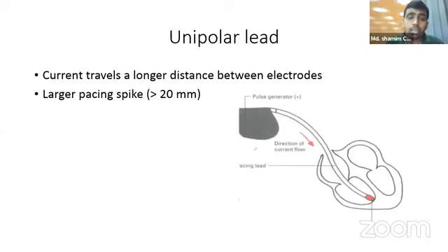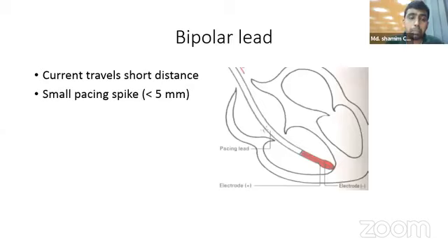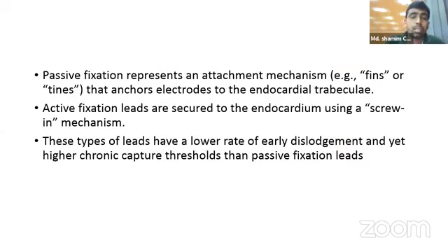This is a pictorial of the unipolar leads, which have larger pacing spike, more than 20 millimeter. And this is a bipolar lead, with the small pacing spike less than 5 millimeter. And the leads are fixed in the atrium and ventricle through two mechanisms, either passive fixation or active fixation. Passive fixation represents an attachment mechanism by tiny tines that anchor the electrodes to the endocardial trabeculae. And active fixation leads are secured to the endocardium using a screwing mechanism.